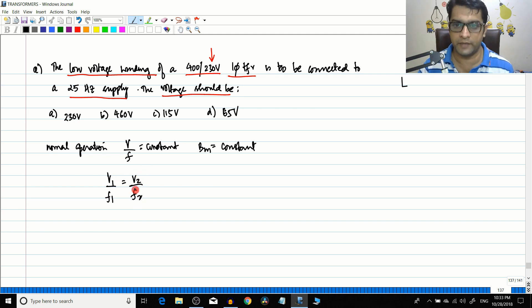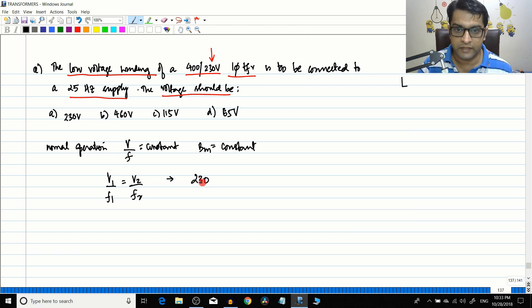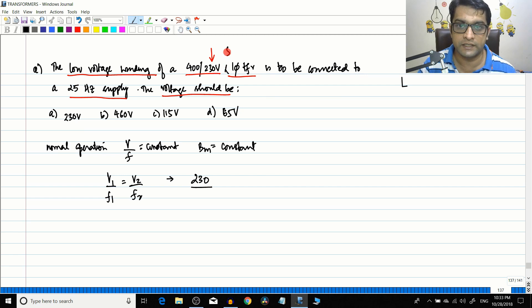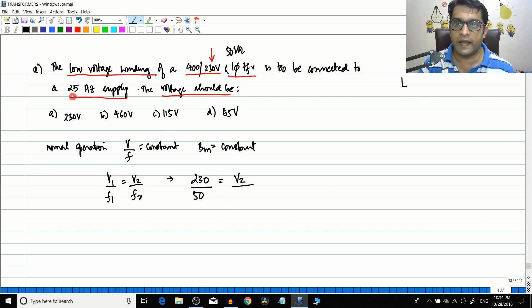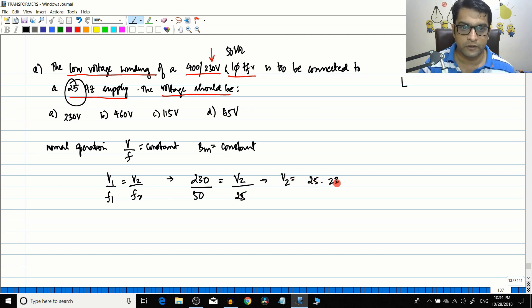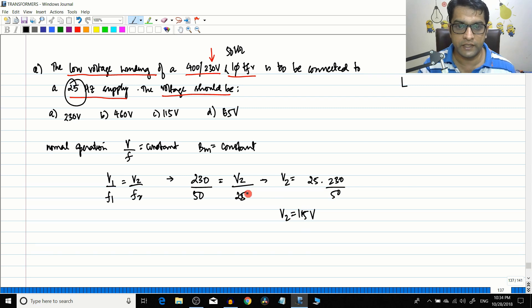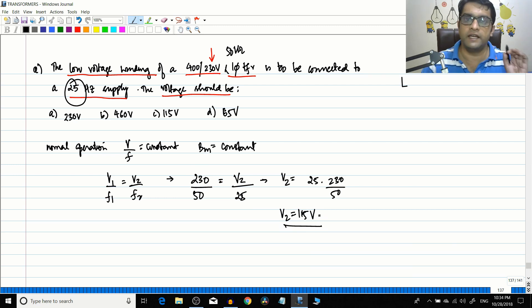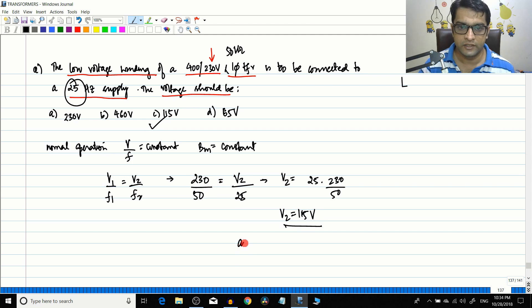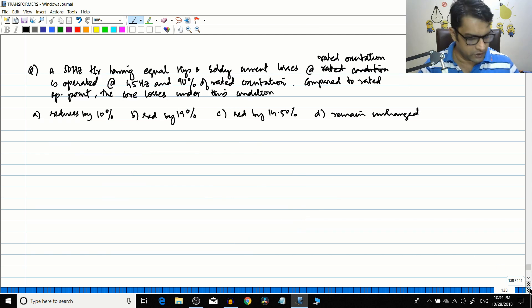Here V1 is 230 volts (the low voltage side) and f1 is 50 hertz for this 50 Hz single phase transformer. The reduced frequency is f2 = 25 Hz. So V2 = (25 × 230) / 50 = 115 volts. If you reduce the frequency by half, you must also reduce the voltage by half to 115 volts, so the transformer works at constant rated flux. The answer is option C.